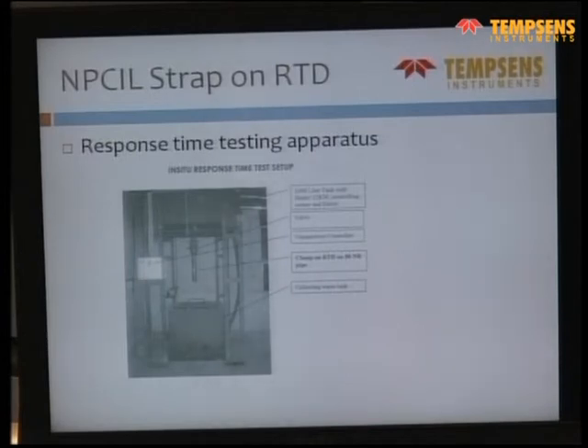So we have to do an in situ test. We have to simulate the same amount of flow that they are going to see in their plant, and we have to offer a response time of less than 20 seconds for each RTD along with the pipe. The temperature changes from ambient to maybe 80 degrees centigrade. The water is heated up in the big tank upside, and when it is falling down with the same kind of flow, the response should be less than 20 seconds. So we have a full simulation for the whole set.